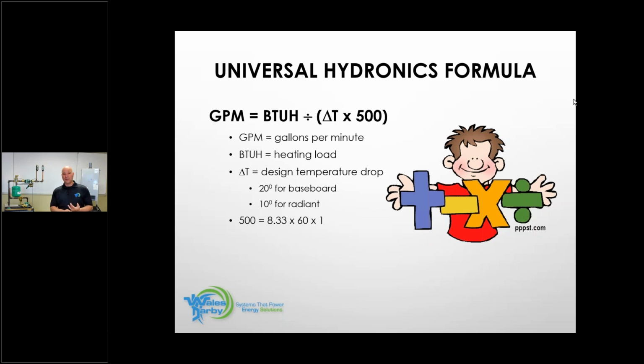We do have a 10-degree delta for radiant. We do most of our designs for radiant around 10. With condensing boilers, you may have a 30-degree delta designed around that condensing boiler because we want it to condense, because that's where they become more efficient. But for today, we're going to stick with a 20-degree delta T. So 20-degree delta T is our number. Write that down. We're going to go back to that.